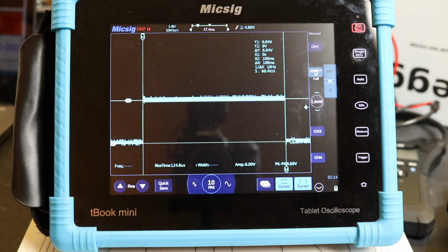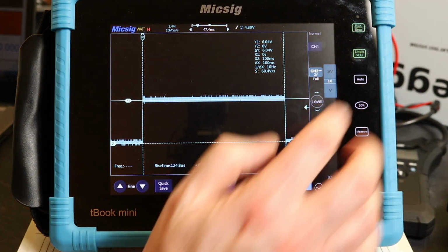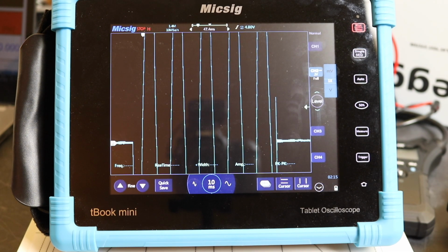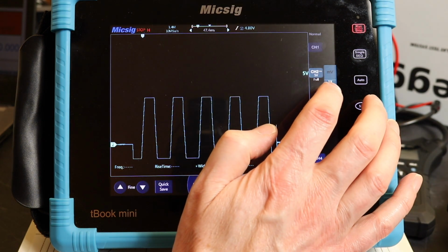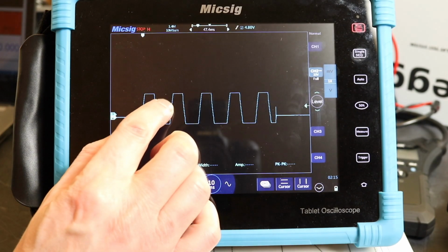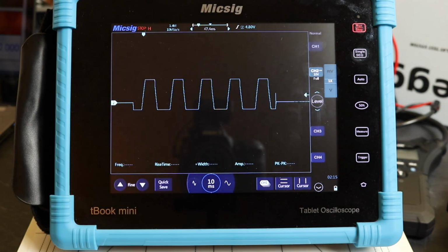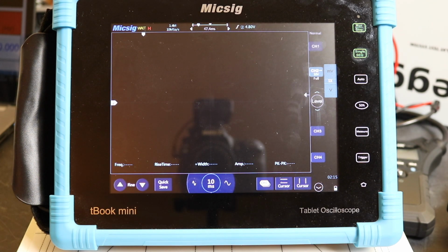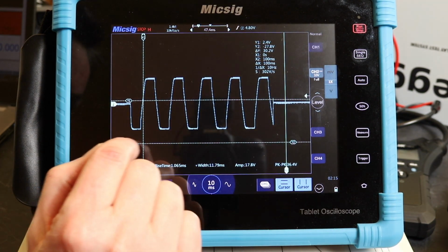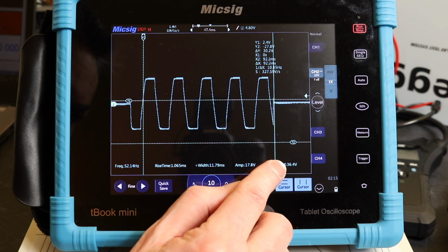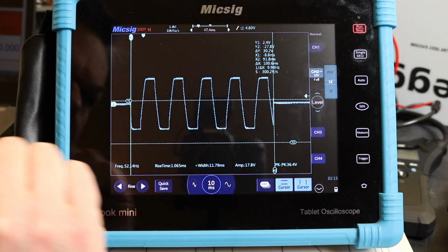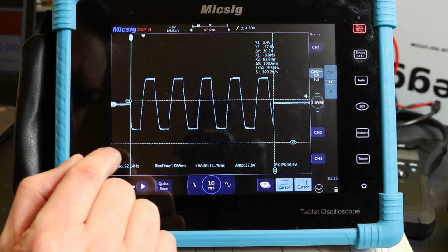And now we need to convert everything to AC. That's AC, we'll reset. Go again. We need to up our voltages, don't we? So we are going on 20 volts on this one. So pretty similar response with the previous one on DC there and the previous AC one. 100 milliseconds. We're 100.6 by the looks of it.